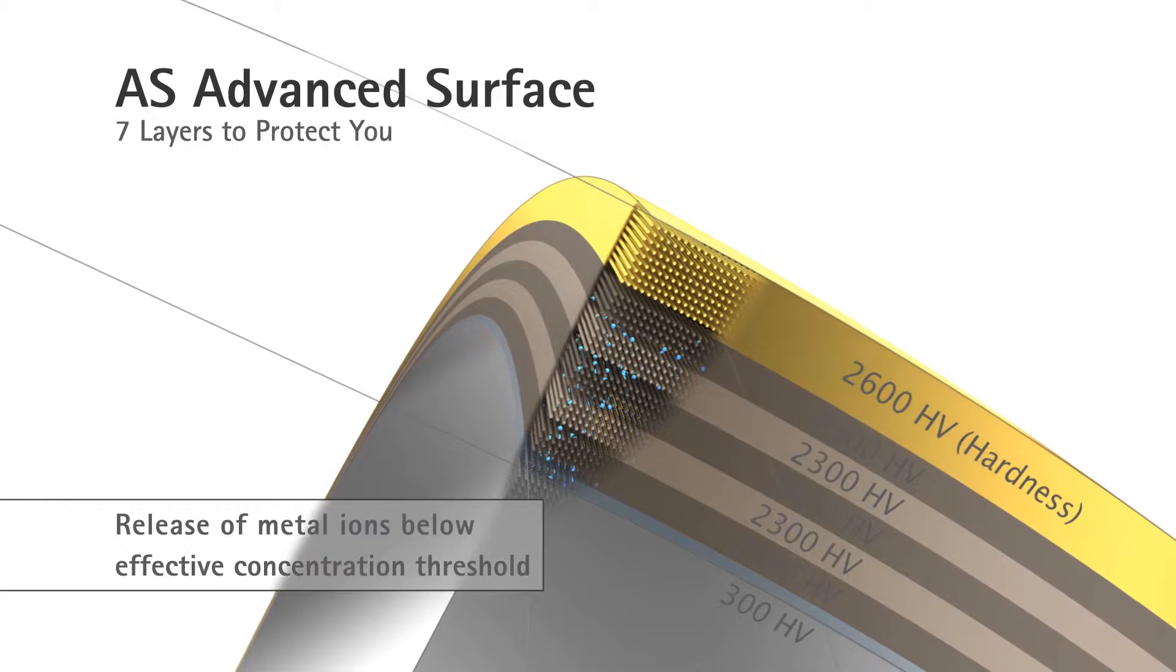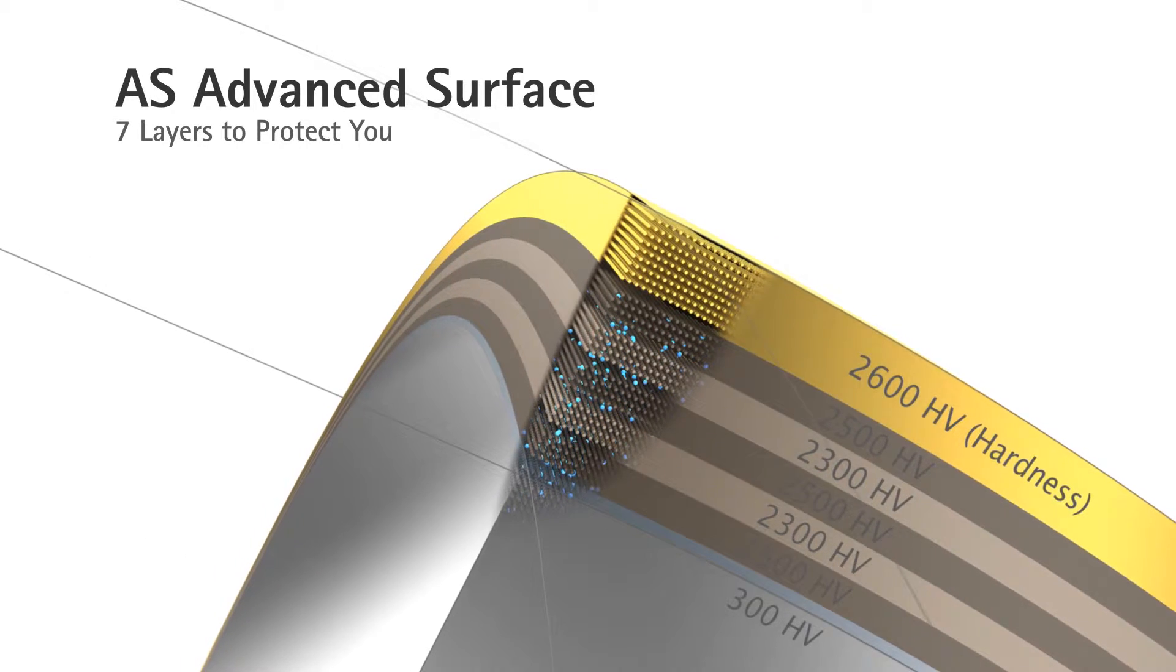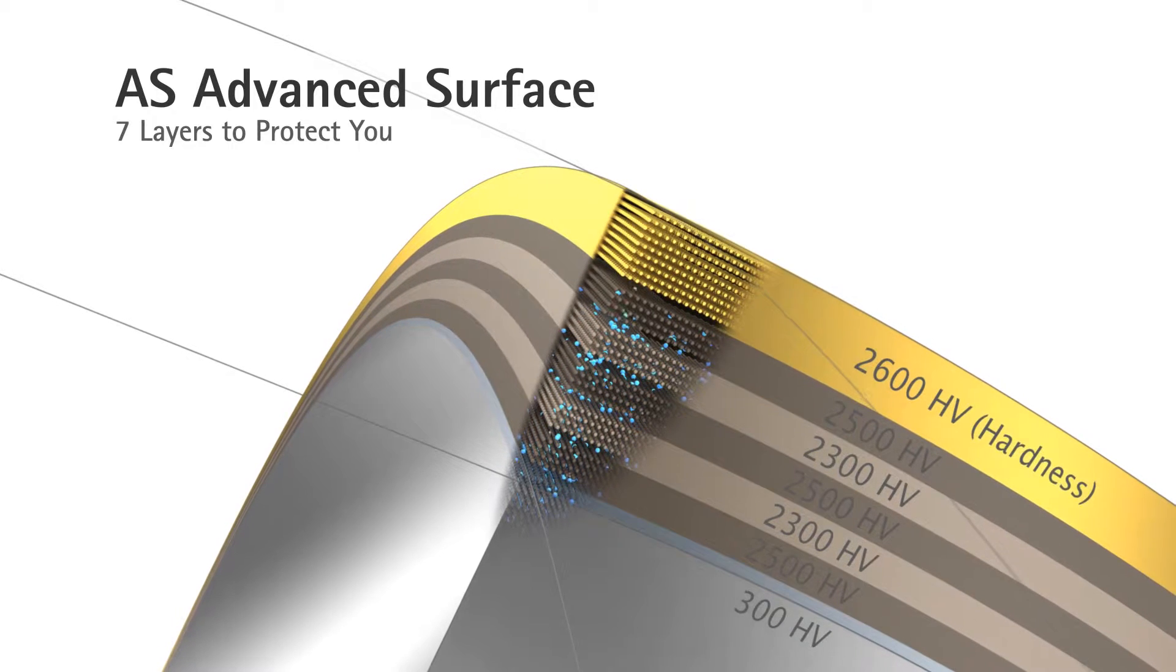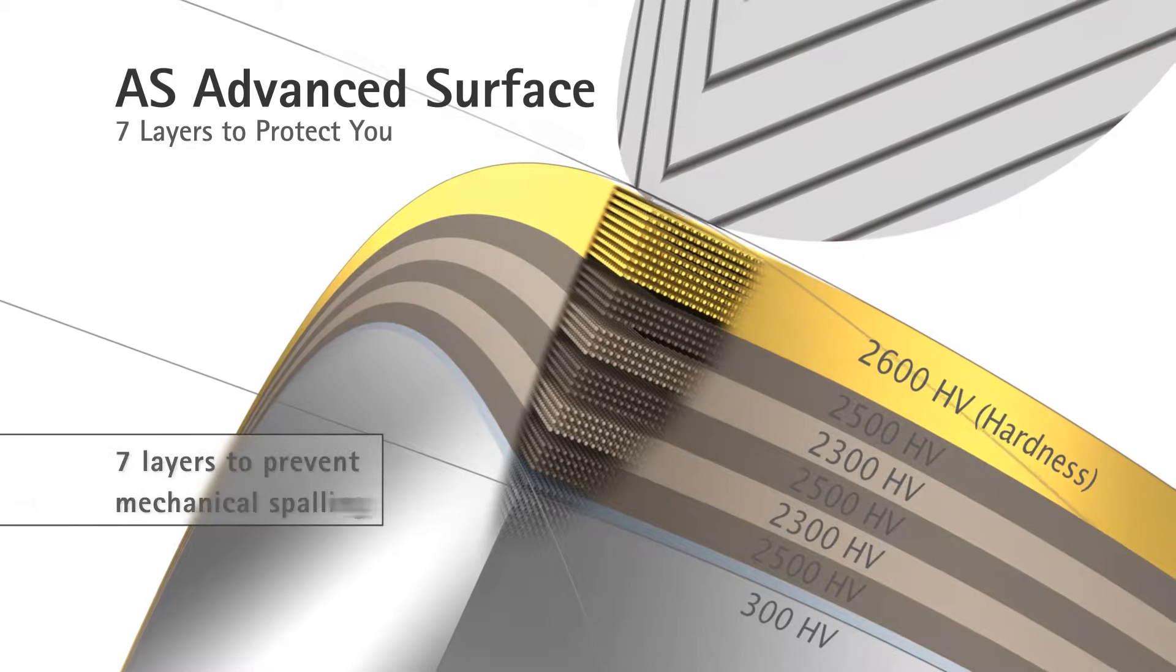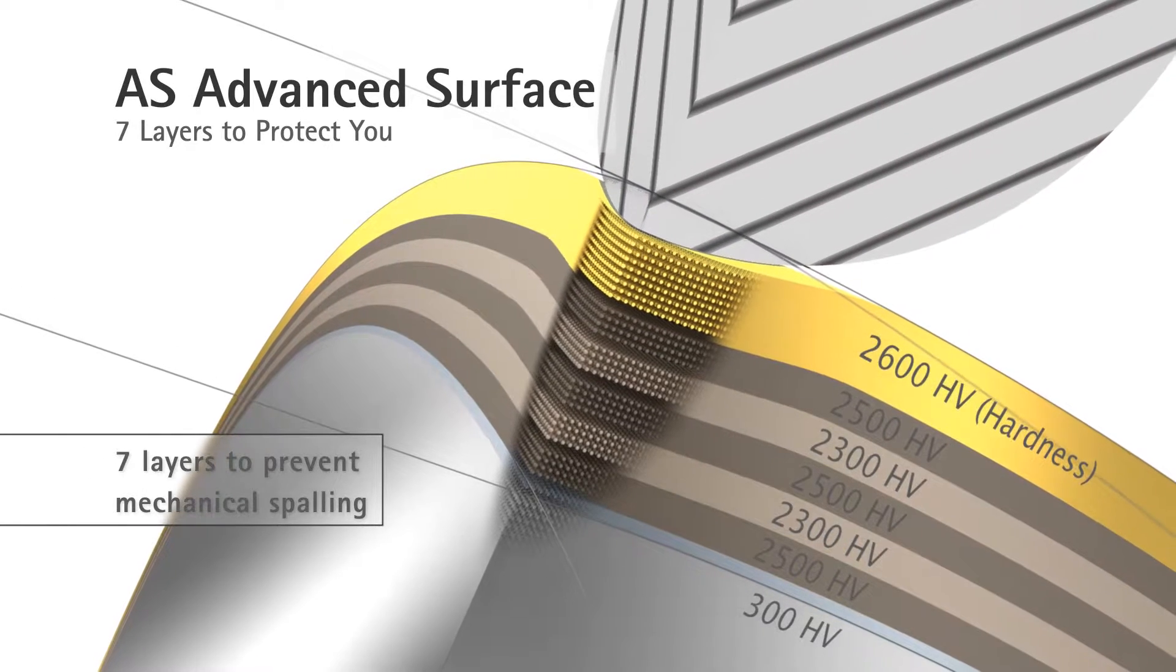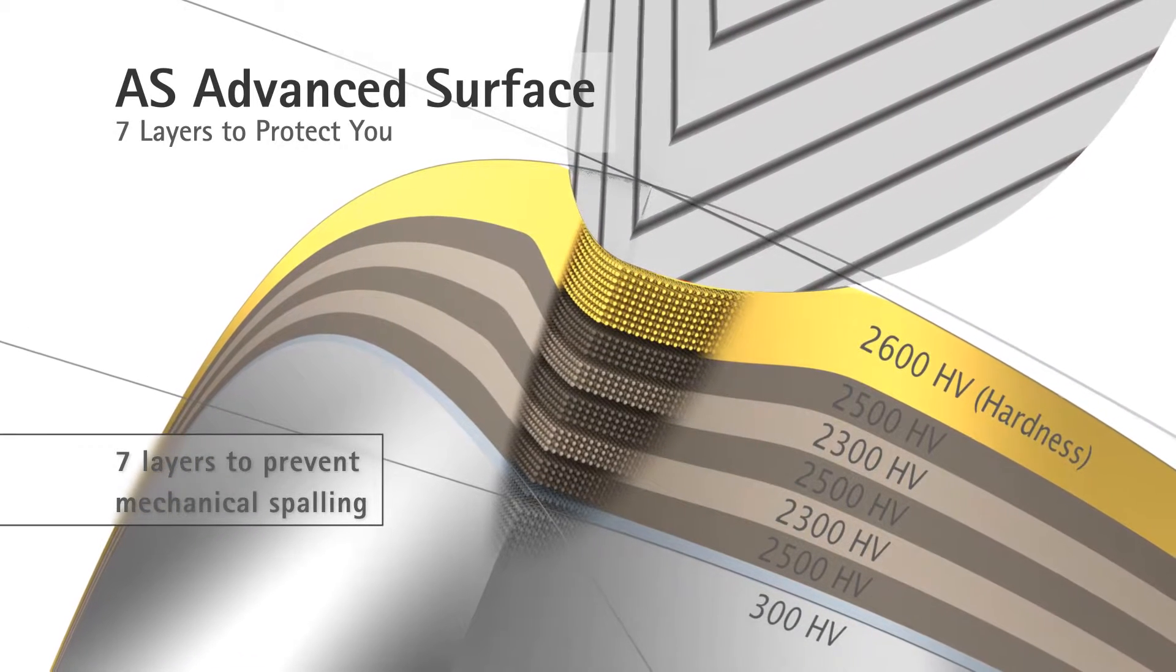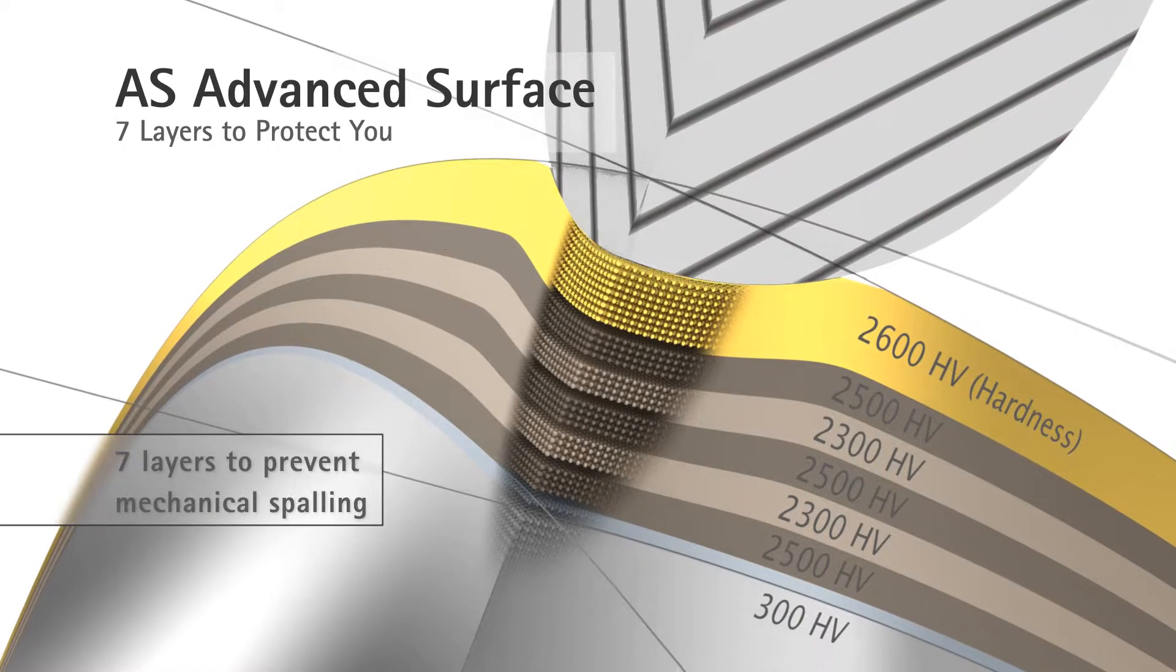This means that implants with an advanced surface coating can significantly reduce the five times higher risk of implant allergy in patients following revision surgery. The rather hard ceramic outer layer on the relatively soft cobalt-chrome substrate prevents a higher risk of the coating spalling, as was previously observed with monolayer coatings.